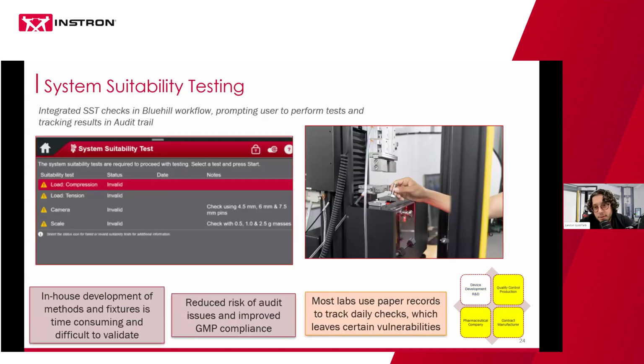And then finally, having the opportunity to go to a lot of labs and see how they're doing testing, especially GMP labs, I keep seeing a lot of places will have a notebook right next to the system. They call it whatever they want, daily check, system suitability. They have an SOP defining their procedure to check that each transducer is working at the start of the day. And that's a more commonly manual practice that is done with pen and paper to record the results.